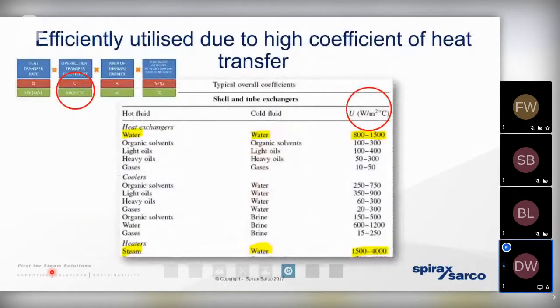And another point that makes steam a very interesting source of heat energy is it's got a very high heat transfer coefficient. That's often referred to as a U value that you may remember from one of those thermodynamic equations that we looked at in previous weeks. It's the speed of heat transfer, the speed at which the energy in the steam passes across the thermal barrier into the process. And you can see that if we're using steam, the speed of heat transfer is about 3 times greater than that of water. So that basically means if we've got a high U value, it therefore means that we need a smaller heat transfer surface area compared to a water-to-water heat exchanger.